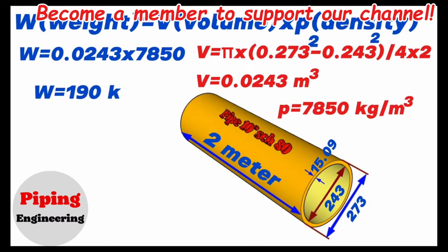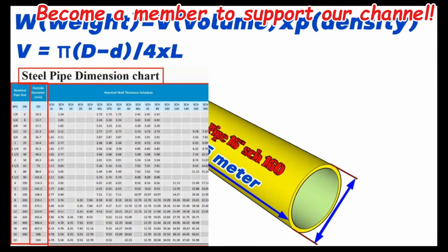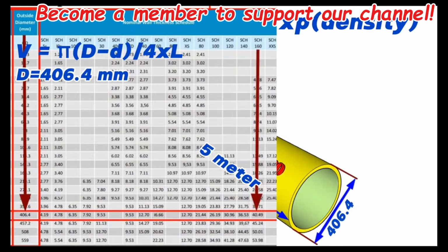Now let's calculate the weight of a 16-inch iron pipe with a wall thickness of 160 and a length of 5 meters. Since I know some of the calculations now, I won't repeat them and will move quickly. We will look at the row showing nominal pipe size 16-inch in the pipe size chart. From the chart, we find that the outer diameter of the 16-inch Schedule 160 pipe is 406.4 mm and wall thickness is 40.49 mm.